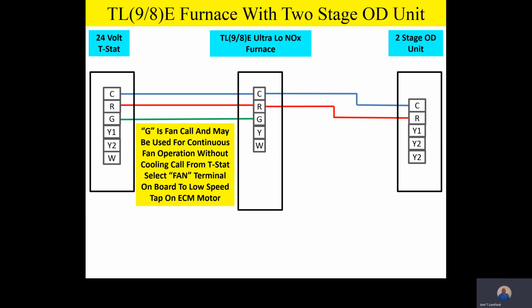Now the fan terminal on the board itself is typically going to be hooked up to a low speed tap on the ECM motor. This is a very nice feature for a fan only call and continuous fan operation. So again, we recommend that on the control board where it says fan, go down and select a low speed motor speed tap so that during a call for continuous fan operation, the fan runs at a nice low constant speed, which is very quiet. It provides great filtration anytime that fan is running. Even though we're not calling for a cooling call, it still is going to run at a very low speed, and it'll give us some wonderful comfort as well as good filtration.